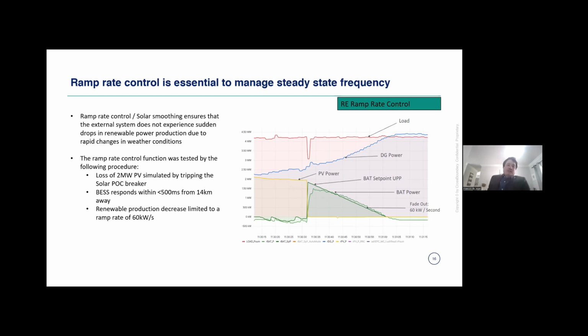So the way that we essentially tested the robustness of this application was by forcibly removing about 2 megawatts of solar PV during operation and allowing the battery to respond and ensure that the ramp rate was limited to 60 kilowatt per second.